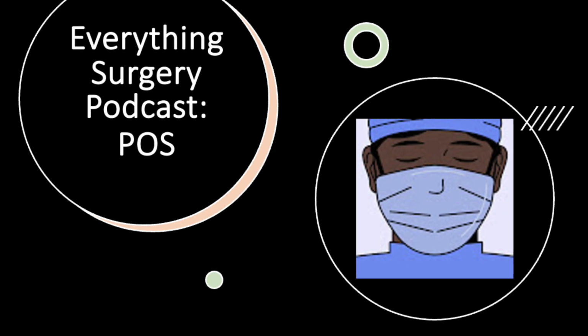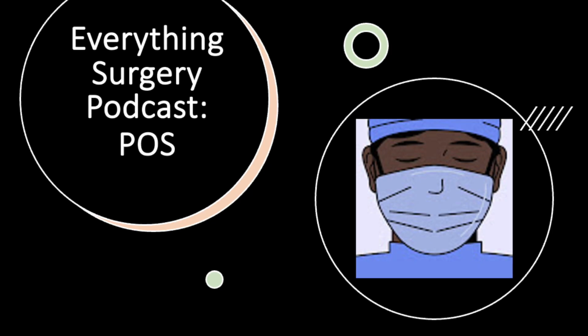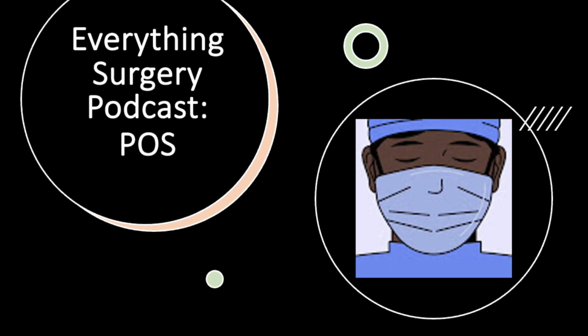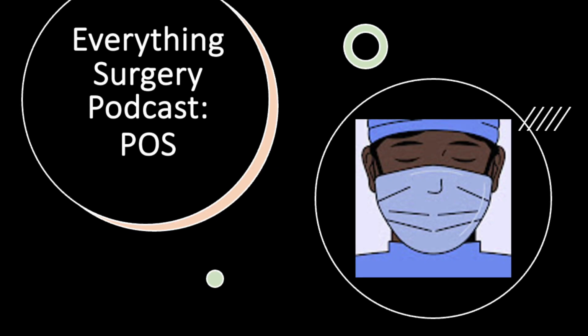Low-temperature hydrogen peroxide plasma systems, such as those branded as Sterrad, use a vacuum to turn vaporized hydrogen peroxide into a plasma field. This generates free radicals that disrupt cell structures, making the method safe for heat and moisture-sensitive items, especially those with lumens like flexible endoscopes. The process is fast and non-toxic, but it cannot be used with cellulose-based materials like paper or linen, or with liquids and powders. There are also limitations on the length and diameter of lumens it can treat.